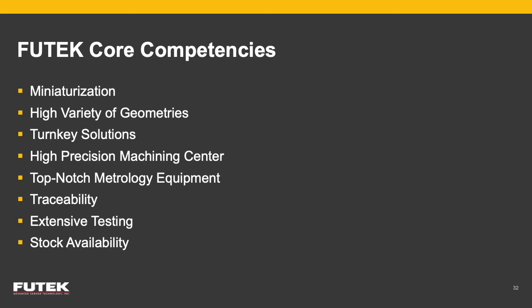Extensive testing, from the design stage with extensive FEA analysis and physical fatigue testing, to the production stage where we perform several in-process inspections and tests such as leakage test for IP rating, temperature compensation test, IR testing, and multiple calibration tests for nonlinearity, hysteresis, and creep.